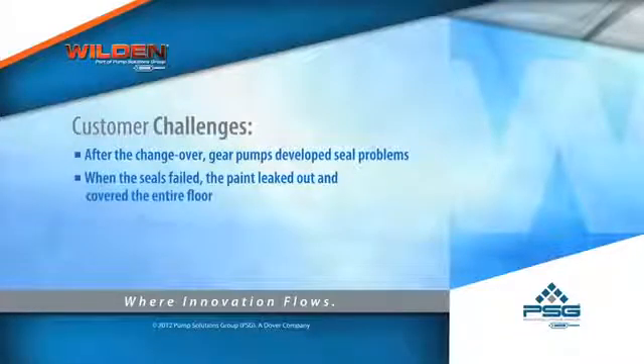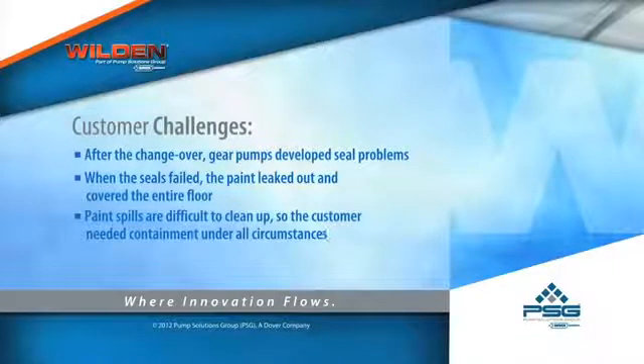These rotary gear pumps had a problem suddenly with the seals. They had leakage. When you have leakage, the product comes out, spills over the floor, and everything is messed up. And you walk through it, and before you know it, everything is under paint. And especially paint is difficult to remove, so you want to contain it in your system. Also from environmental ways, of course, if you have paint in your environment, you don't want it. That's the idea with replacing the pumps.